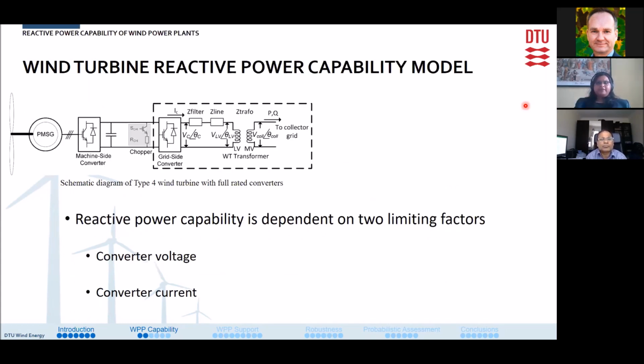Before going into the reactive power capability model for wind power plants, we would like to develop the model for wind turbines. Here, if you can see my cursor, this is the schematic diagram of type 4 wind turbines with full rated converters. Typically, in type 4 wind turbines, the reactive power is supplied by the grid side converter, and it is mainly dependent on the grid side converter parameters. The two main limiting factors are converter voltage and converter current. We can see here that the wind turbine is connected to the wind power collection grid through a step-up wind turbine transformer. Sometimes there can also be a filter or impedance in between the converter and the transformer.